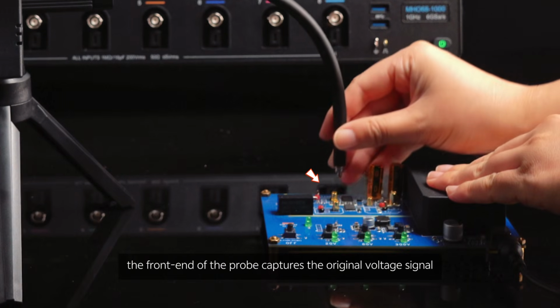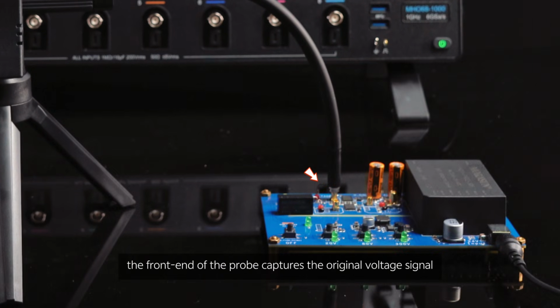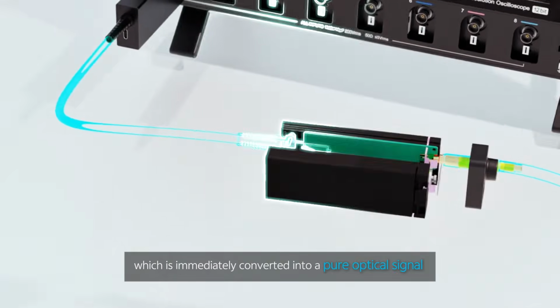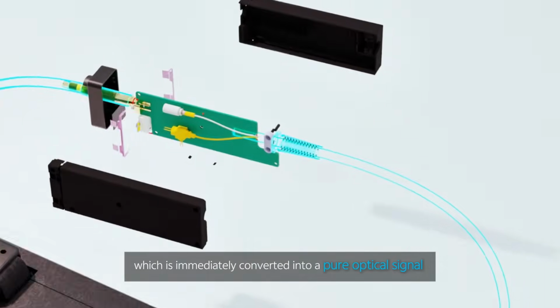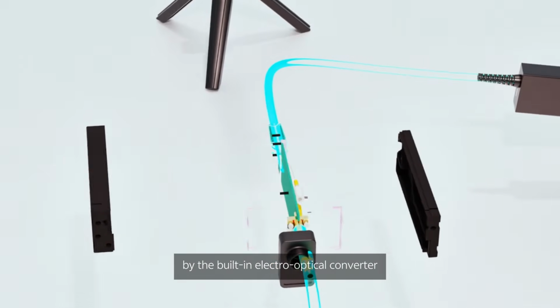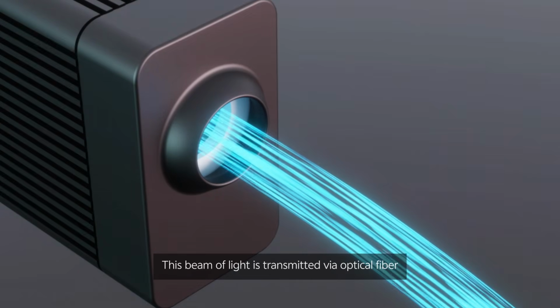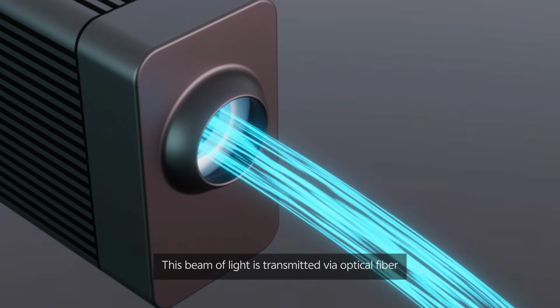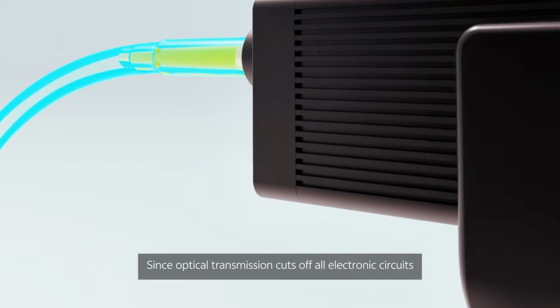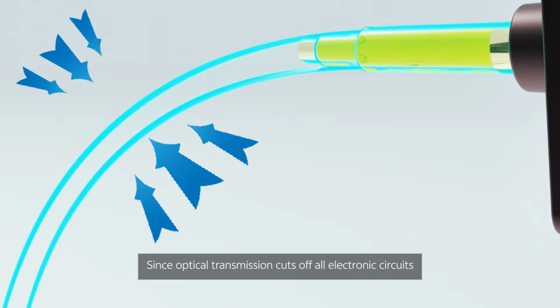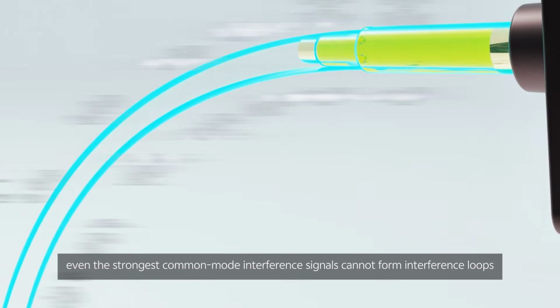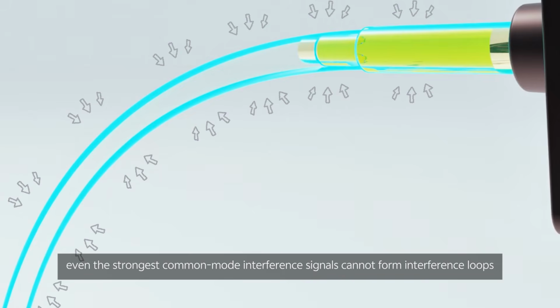During measurement, the front end of the probe captures the original voltage signal, which is immediately converted into a pure optical signal by the built-in electro-optical converter. This beam of light is transmitted via optical fiber. Since optical transmission cuts off all electronic circuits, even the strongest common mode interference signals cannot form interference loops.